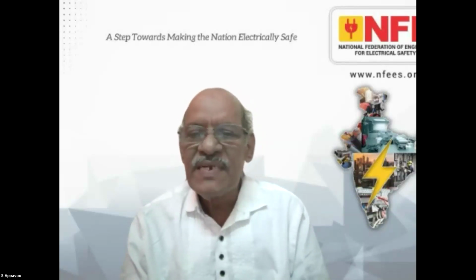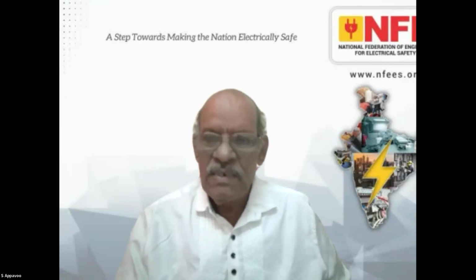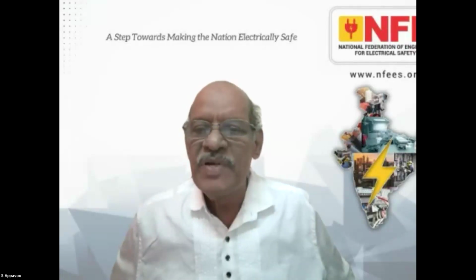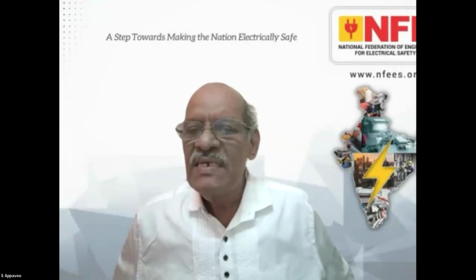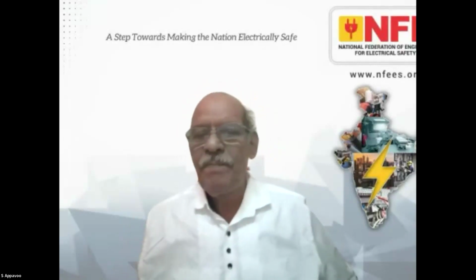Okay. One question from Chandrasekhar: do we need to include SPD in all power distribution panels if they are placed under zone 2 or zone 3? If it is placed in zone 2, or in zone 3, or if it is coming from zone 2 to zone 3, then you are supposed to have SPDs in that place. Or suppose you are classifying the whole area as zone 2 and there is no zone 3, then you don't need to have them. But if it is coming from zone 2 to zone 3 and there is a panel for power distribution, then you are supposed to have SPDs.